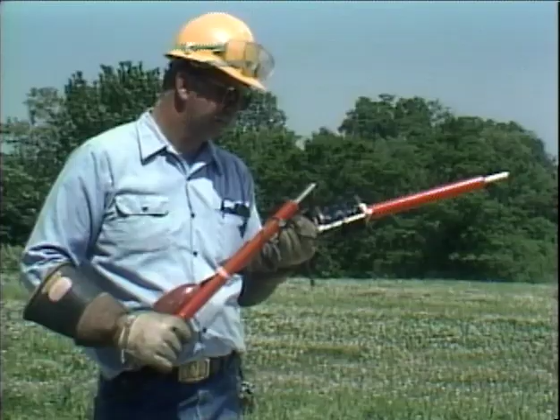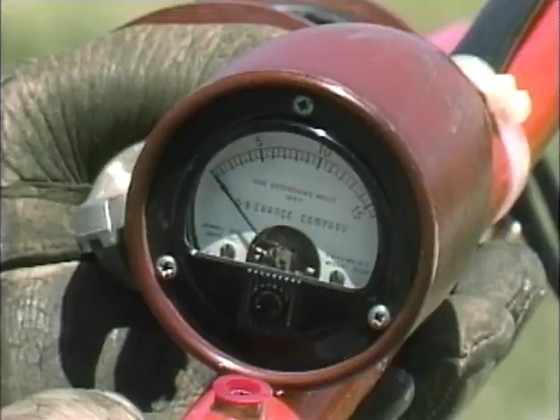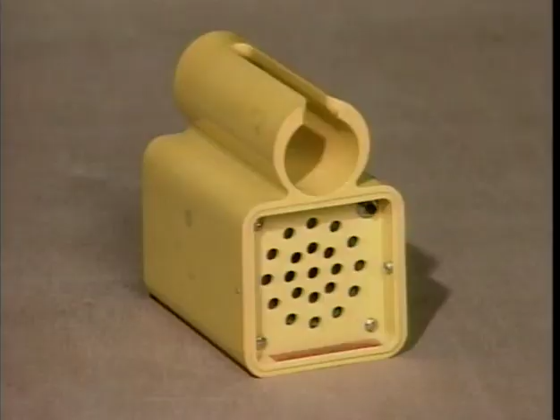So before you use a tester, make sure the circuit you're testing is within the correct operating range of the device. Now, you also need to inspect a tester both before and after you use it to make sure it's in good working condition. If a tester is damaged, it could give you an inaccurate reading. And to test a circuit properly, you should use a tester on all the lines at the immediate work site. Discovering one line in a circuit is dead is no indication of the status of other lines. Under certain conditions, one line may be dead while other lines on the same circuit may be live. So it's important to test each line to confirm that the circuit is de-energized.